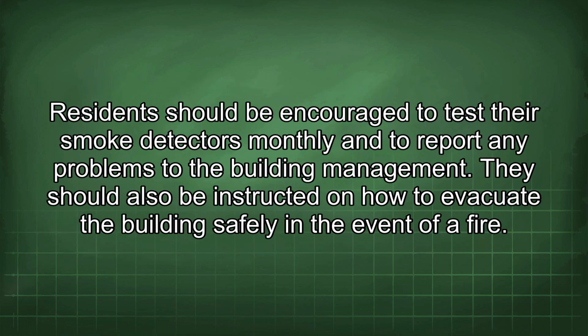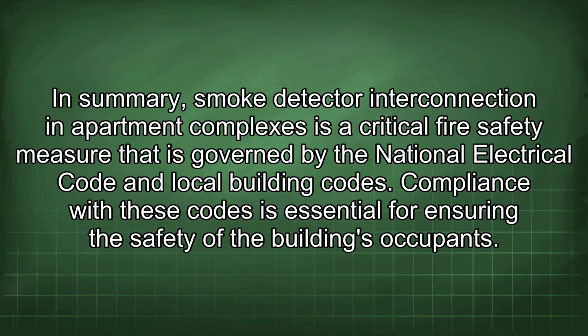Residents should be encouraged to test their smoke detectors monthly and to report any problems to the building management. They should also be instructed on how to evacuate the building safely in the event of a fire. In summary, smoke detector interconnection in apartment complexes is a critical fire safety measure that is governed by the National Electrical Code and local building codes. Compliance with these codes is essential for ensuring the safety of the building's occupants.